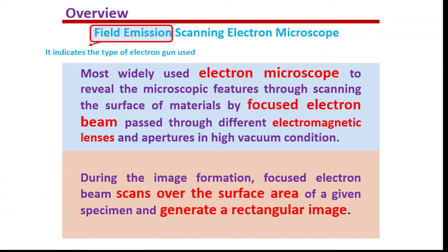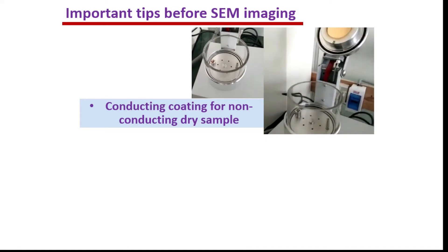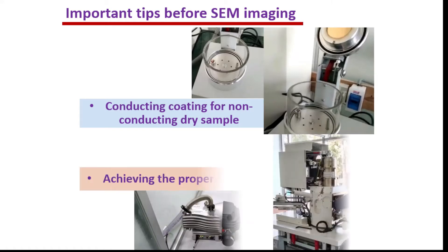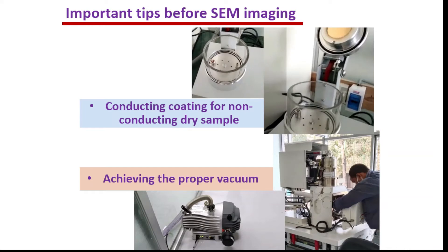For image formation, the focused electron beam scans over the surface of the given specimen and generates a rectangular image. For better imaging, the sample should be dry enough and coated with a conductive layer to avoid charging of the sample. For non-conductive samples, it is safe to coat them with a protective coating like gold coating. Proper vacuum conditions are required; otherwise the total system will not function properly.